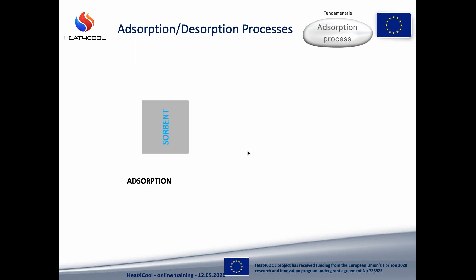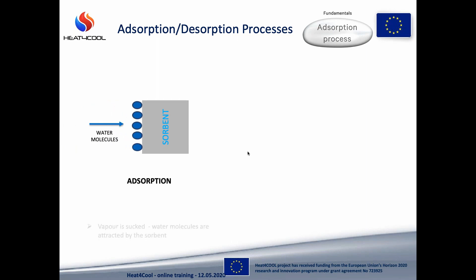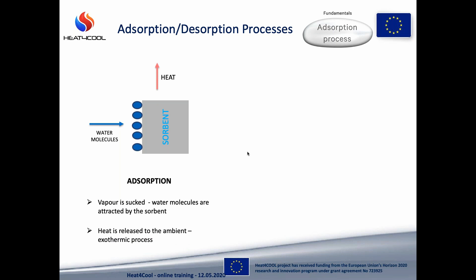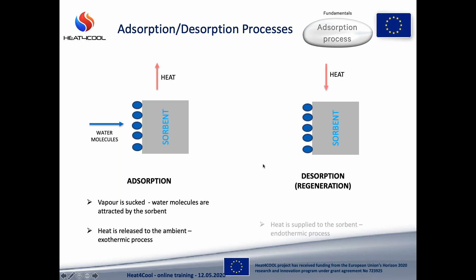Let's start with adsorption. During this process the sorbent attracts the water molecules — in other words it sucks in the vapour. At the same time heat is released to the ambient, therefore we call this process exothermic. After some time the sorbent gets saturated with water, and if we want to dry it again we have to force the water molecules to leave. We can do it by heating up the sorbent, and this process is called desorption or regeneration. Because we are adding heat, we call this process endothermic.